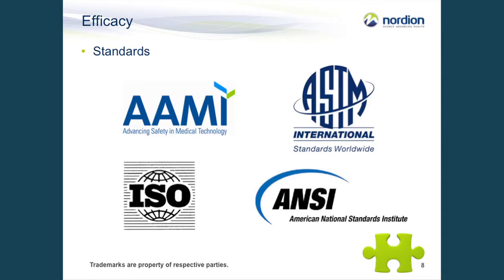Radiation processing, dose delivery, dose setting, and dosimetry measurements are well understood, and there are several standards and guidance documents available through ANSI, AAMI, ISO, and ASTM, including the 11137 series of standards, sterilization of healthcare products, radiation, on development, validation, and routine control of a sterilization process in part one, and on dose setting in part two. ASTM Committee E61 has a series of standards, practices, and guidance documents available on dosimetry system selection, calibration, dose mapping, and use in gamma facilities.